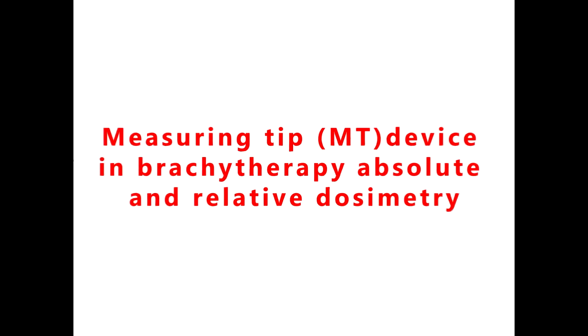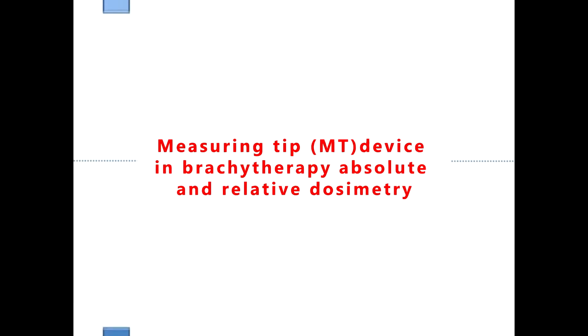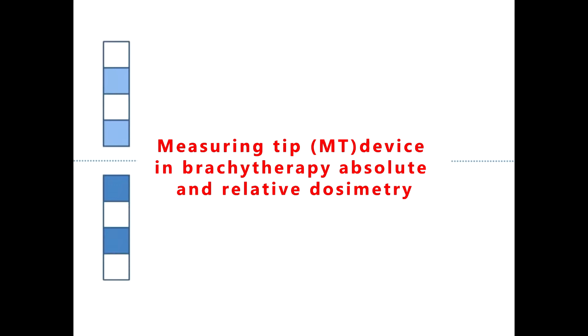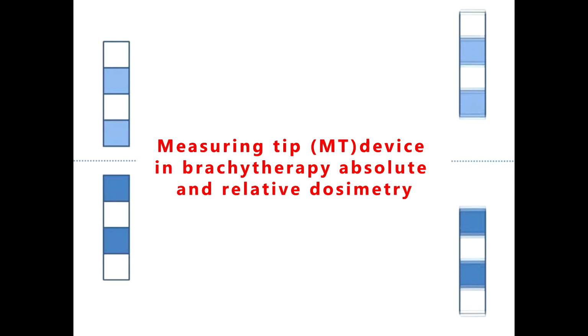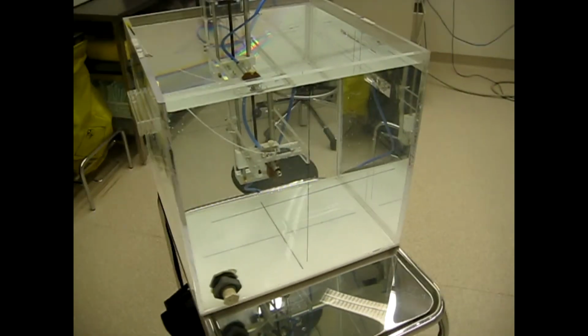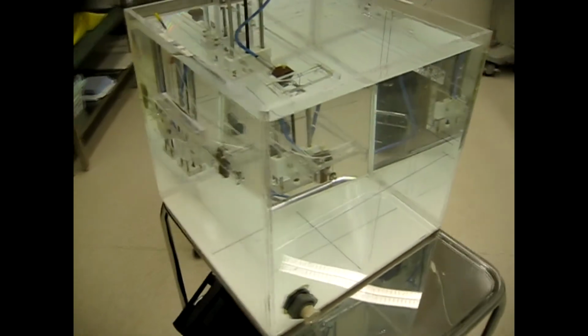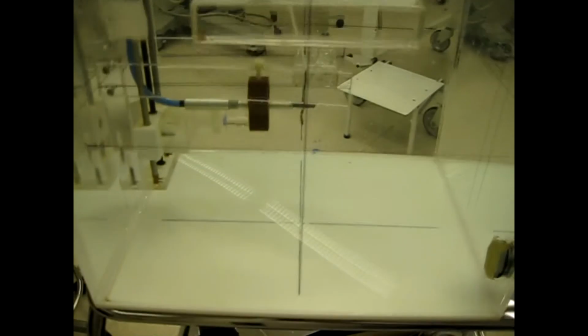Today we are speaking about a measuring tip or MT device for relative and absolute dosimetry in brachytherapy, where precision of position in the ionization chamber is even more significant than in teletherapy. Here I will talk about the brachytherapy water phantom, where the main ideas are implemented.